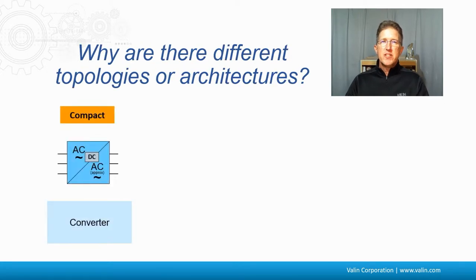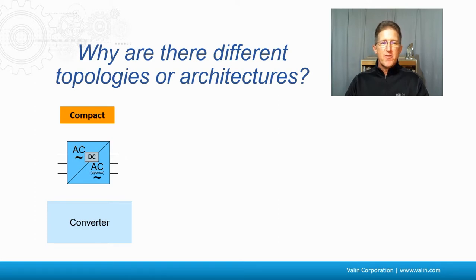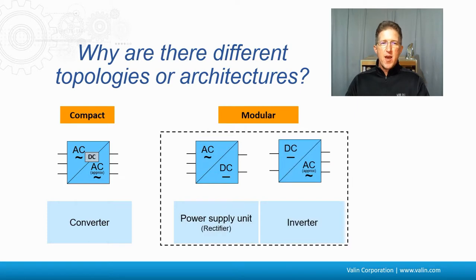Why are there different topologies or architectures? Here are a couple to consider. There's what some suppliers call 'compact,' where the AC is converted to DC, which is then converted back to an approximated AC that goes out to the motor — that's the converter. You can break that up so that the AC-to-DC conversion is a power supply unit, rectified internally and separated into two units. The DC then becomes the AC that goes out to the motor, and that's called an inverter.